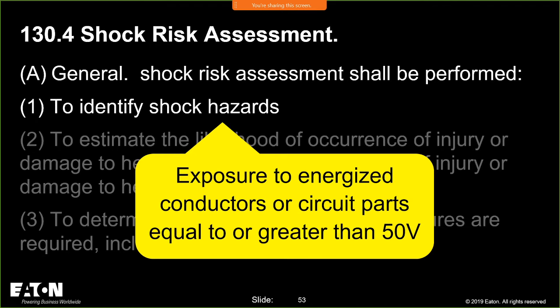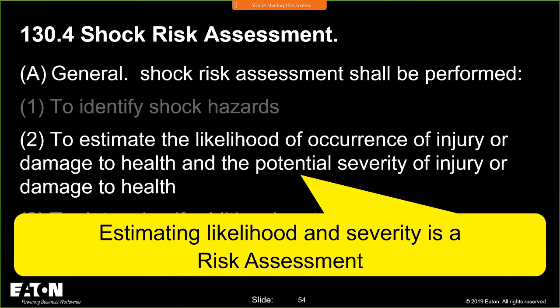You may be very qualified to work on a residential panel board, but you're probably not qualified at all to work on a switchboard because you don't understand the equipment. You don't know how to recognize what may be energized, what may not be energized when things are turned on and off inside that equipment. You may kill power to that equipment and enter it not realizing that it has a UPS that has 120 volts running inside the equipment, and not realize that you have another source of voltage because there's a UPS, a battery system inside there to operate relays and things of that nature. So equipment can get complicated, and we have to make sure that we are educated on the equipment upon which or within which we're working.